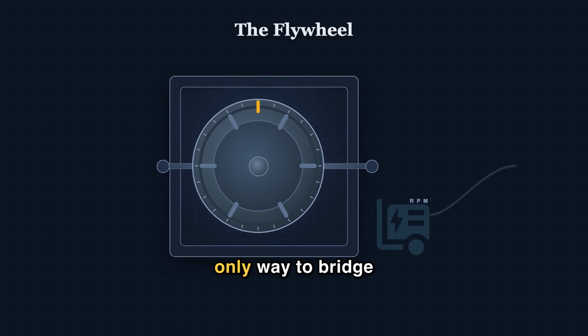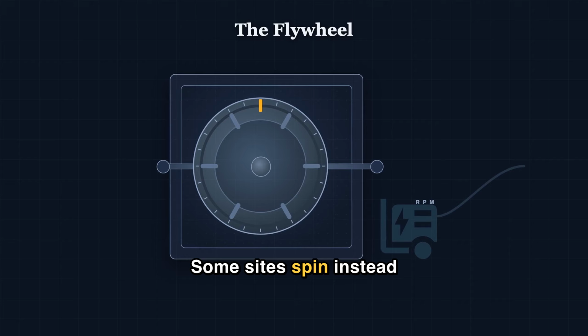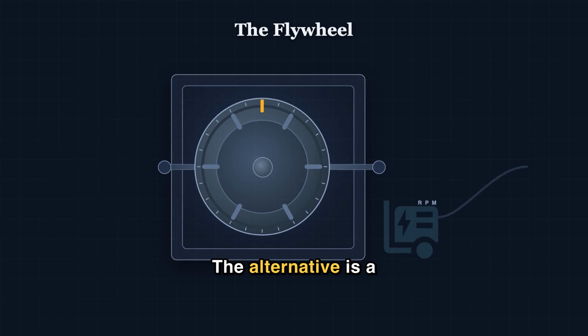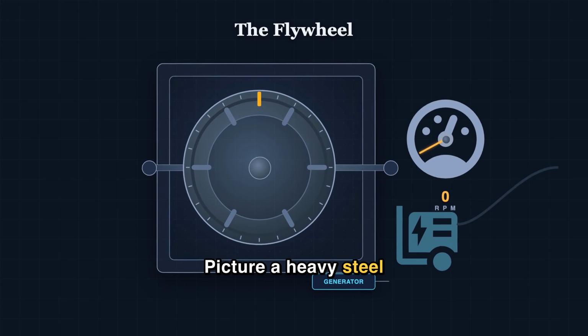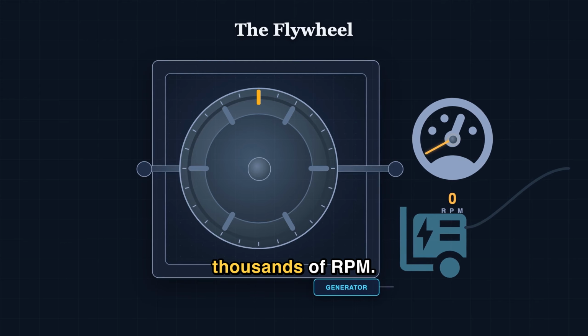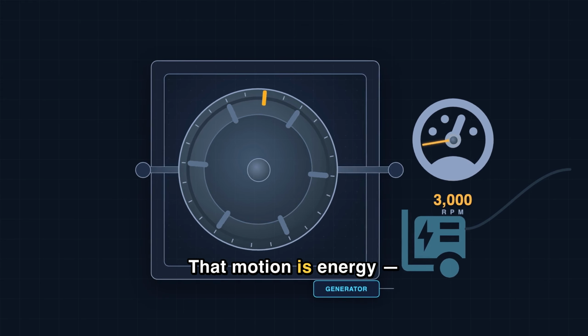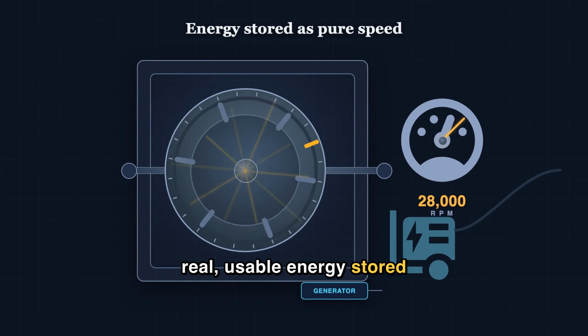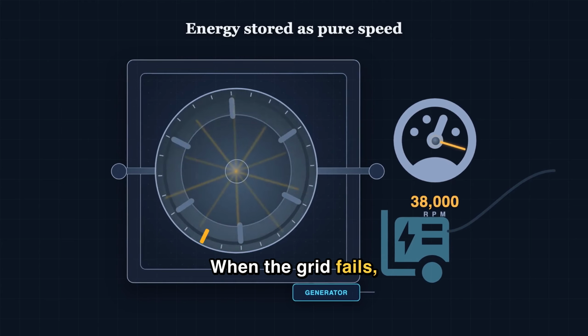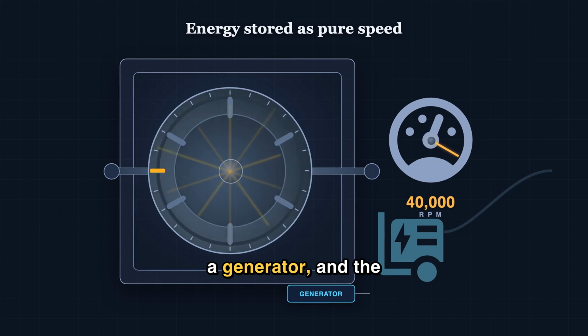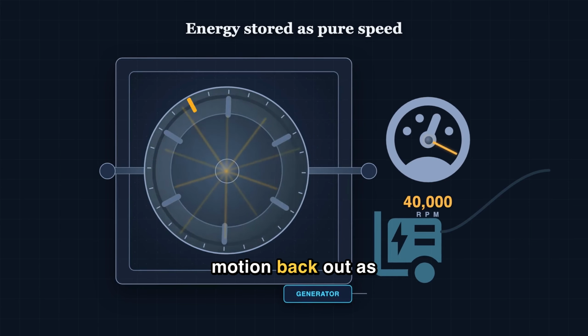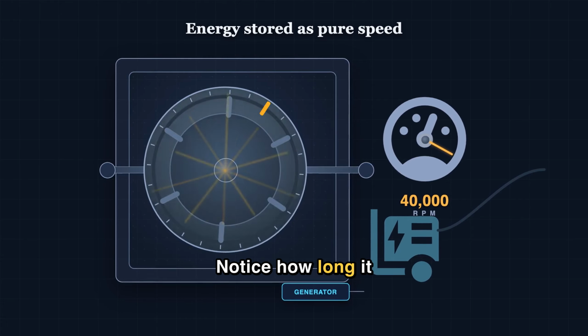But batteries aren't the only way to bridge the gap. Some sites spin instead of charge. The alternative is a flywheel. Picture a heavy steel rotor spinning in a near vacuum at tens of thousands of RPM. That motion is energy, real, usable energy stored as pure speed. When the grid fails, that spinning mass drives a generator, and the slowing rotor pours its motion back out as electricity.